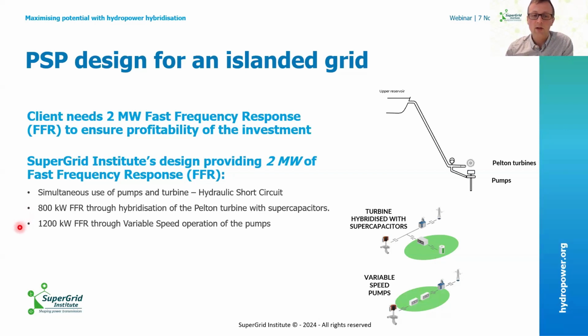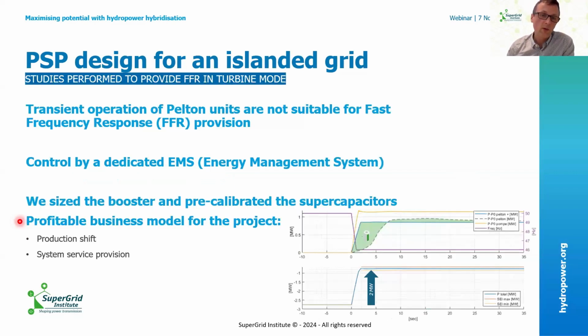Simultaneously, we suggested a change in the design of the pumps, moving from fixed speed to variable speed, which enables providing regulation in pump mode, and obtaining 1,200 kilowatts of fast frequency response with the variable speed pumps. We also suggested to repower the pumps slightly, but still staying within catalog pump sizing. So, as I was just saying, doing so we're able to provide 2 megawatts of fast frequency response, 800 kilowatts from the hybridized Pelton turbines, as you can see here.